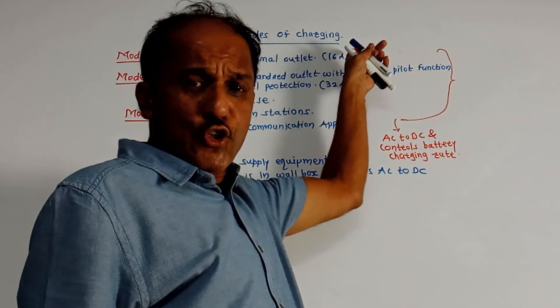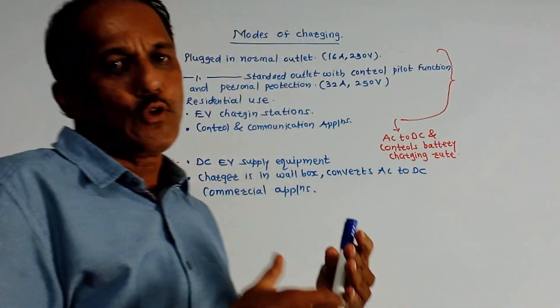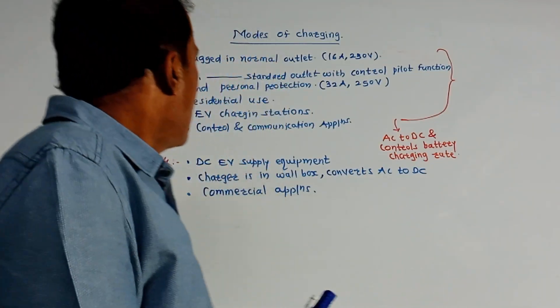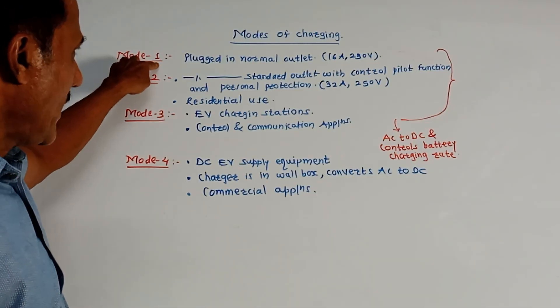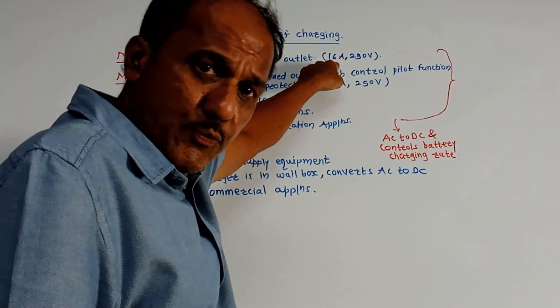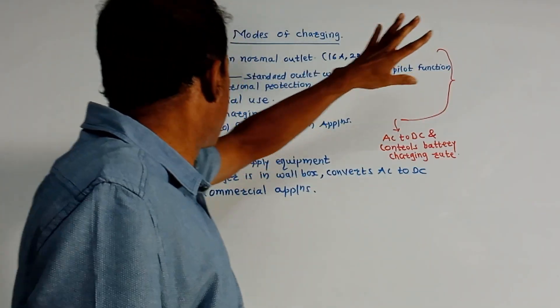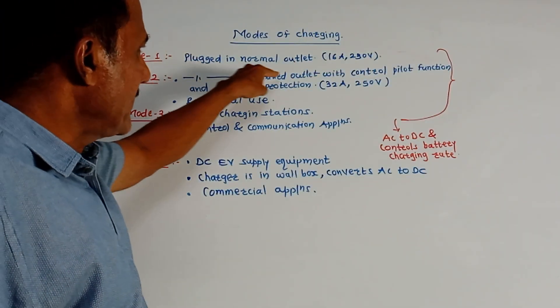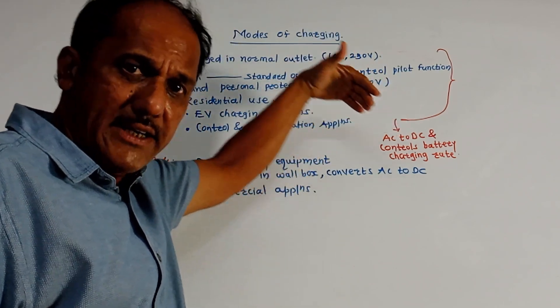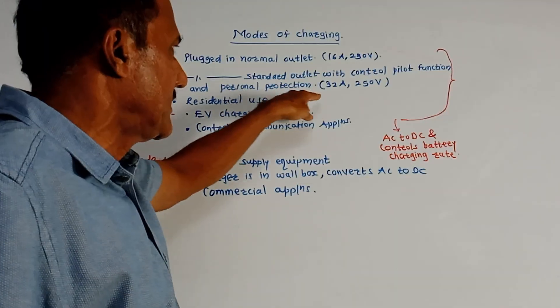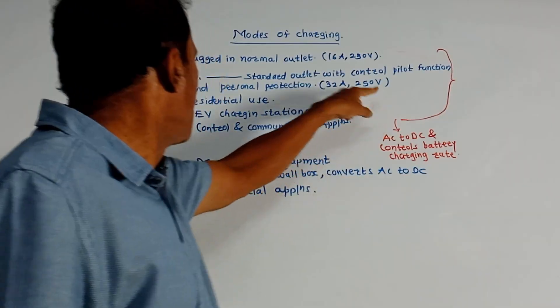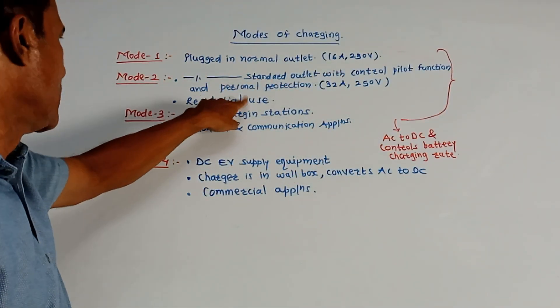The next part is modes of charging of EV batteries. You may expect exam questions on the different modes of charging an EV. There are basically four modes. Mode 1 is plugged into a normal outlet; specifications for single phase are 16 amperes and 230 volts. Mode 2 is plugged into a standard outlet with a control pilot function and includes a personal protection system; specifications for single phase are 32 amperes and 250 volts, and it is usually preferred for residential use.